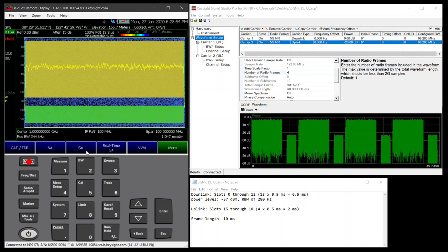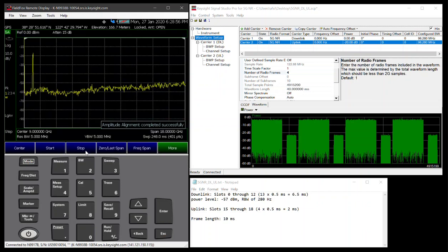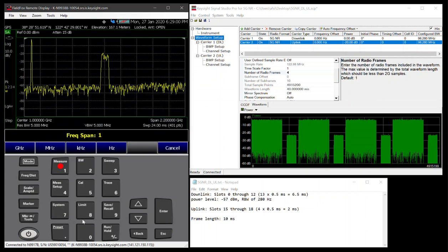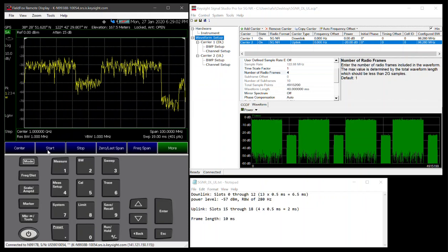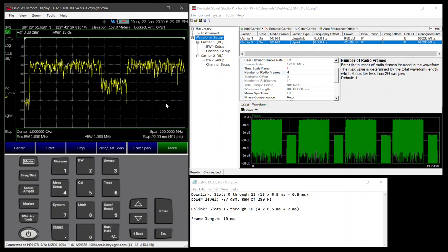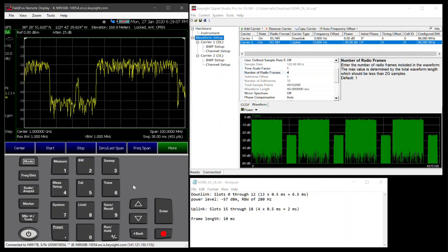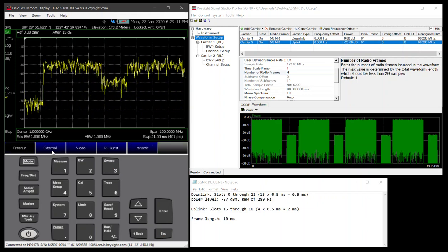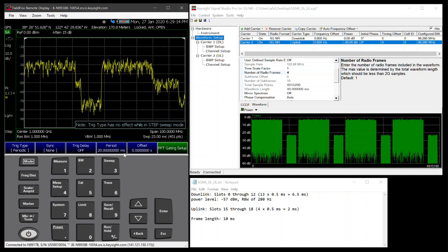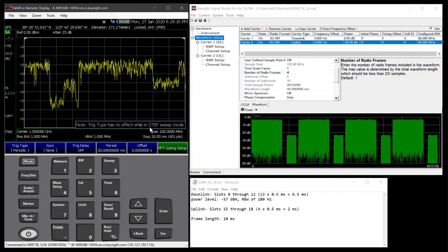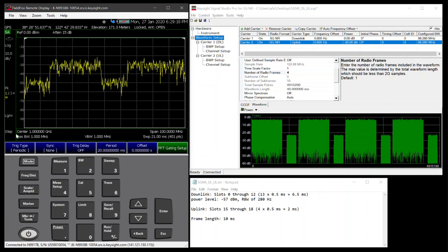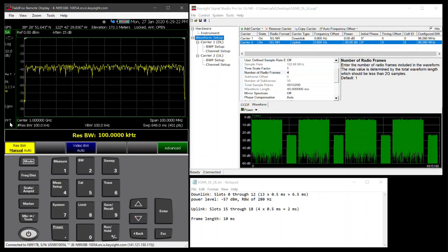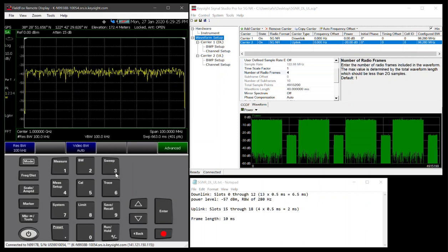Now let's go ahead and look at this in SA, which is where you're going to want to be looking at it, and we'll do 1 gigahertz. And I set it up for an FR1 of 100 megahertz. That's what I just set up here. Then we go into sweep trigger setting, and I'm going to set it up to periodic trigger. And it says in step mode, it doesn't work. What it really needs is to be in FFT mode. So I'll drop the res bandwidth, and at 100 kilohertz, this is FFT mode.